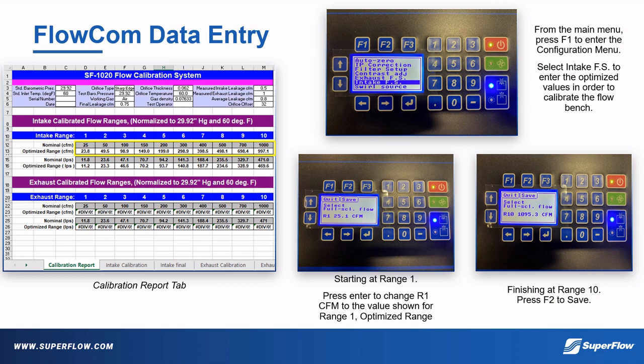In this video, we used intake calibration as an example for instructive purposes. It should be noted that exhaust calibration is performed in the same manner using the Exhaust Calibration tab, with the FlowCom set in exhaust mode. The one caveat to this is the calibration plates used must be placed with the identification number facing down instead of facing up. The reason they are placed facing down when in exhaust mode is because the machined edge of the holes on the plates can have a slight effect on the flow rate measurement.